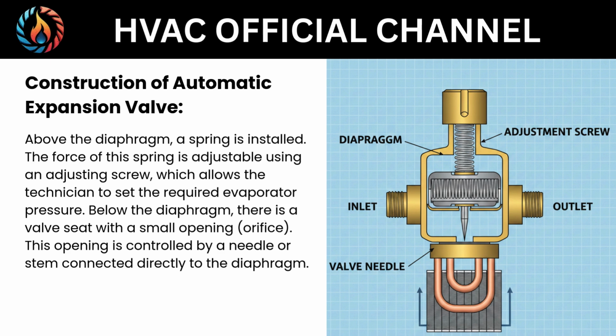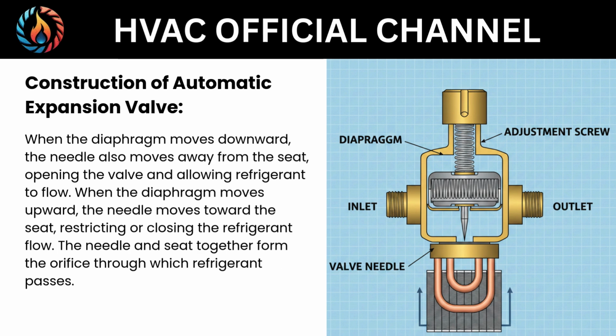This opening is controlled by a needle or stem connected directly to the diaphragm. When the diaphragm moves downward, the needle also moves away from the seat, opening the valve and allowing refrigerant to flow. When the diaphragm moves upward, the needle moves toward the seat, restricting or closing the refrigerant flow. The needle and seat together form the orifice through which refrigerant passes.